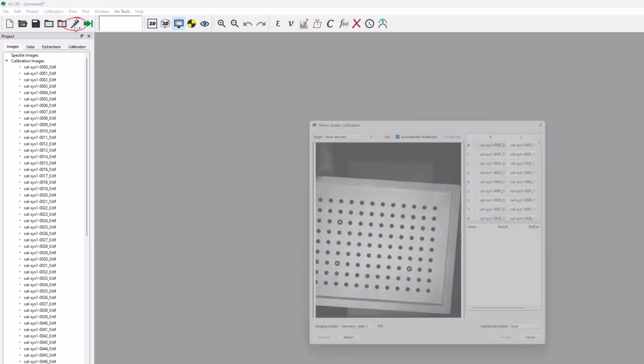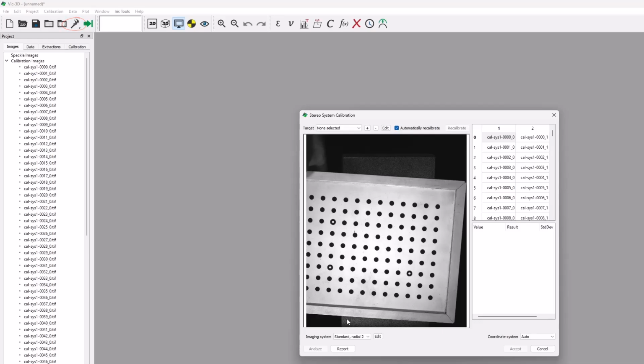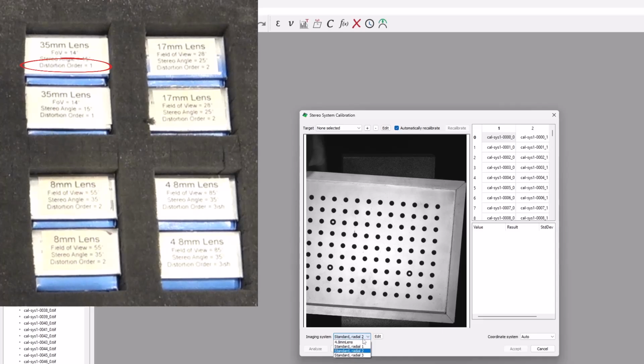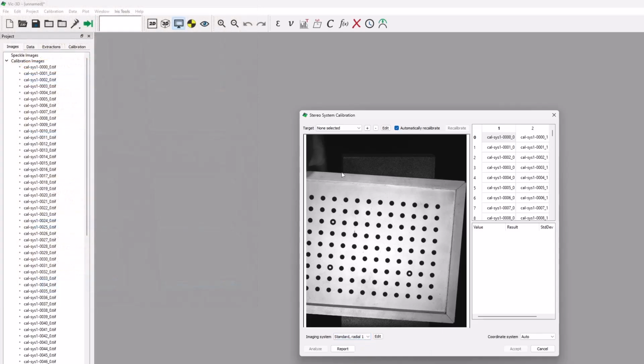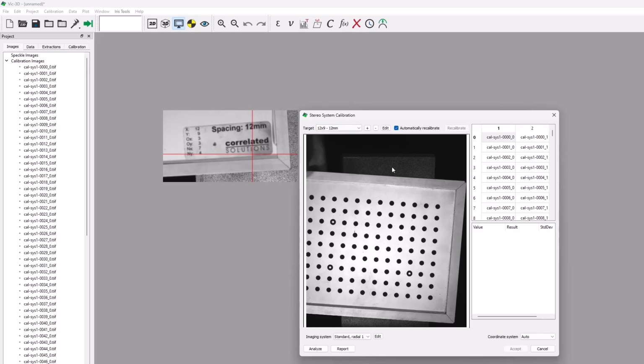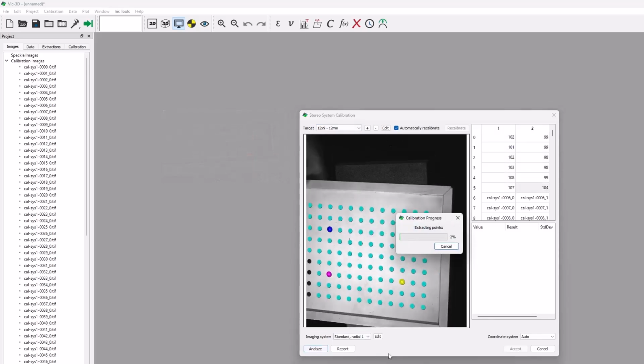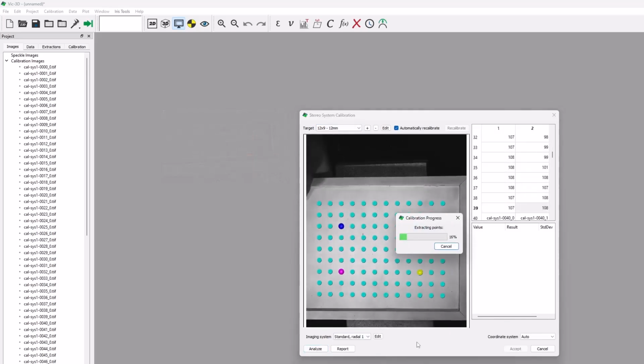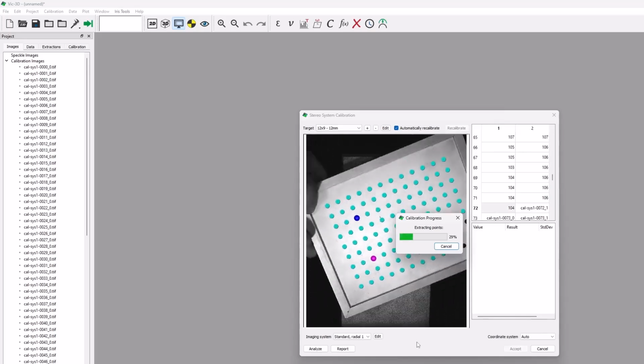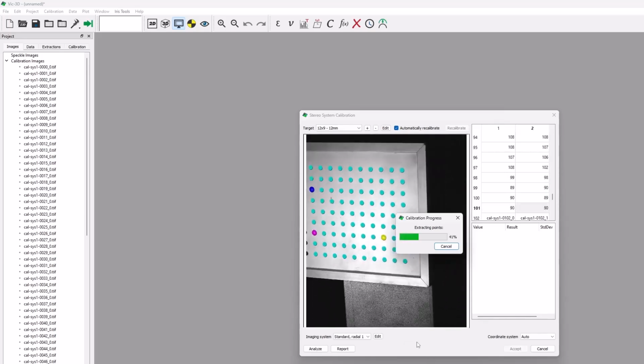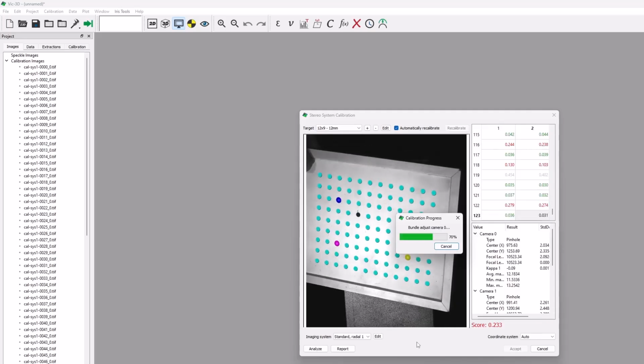Click on the little vernier caliper doohickey to set up our calibration. Imaging system should match what was on the lens box, in our case Order 1. The target is 12mm. Press Analyze. After some time, the software will analyse all the cal images and present a score. This score needs to be under 0.1, however I prefer to use 0.05 as a target score.